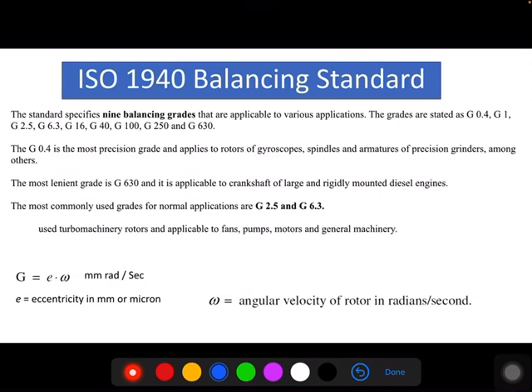For any industries, the main balancing standard used is ISO 1940 for balancing of fans, rotors, pumps, or any rotating equipment. This standard has mainly nine balancing grades that are applicable for various applications. These grades generally start from G0.4, G1, G2.5, G6.3, G16, G40, G100, G250, G630.